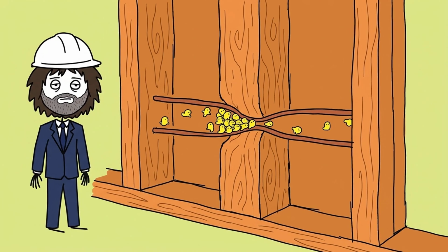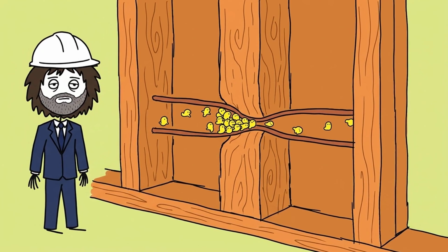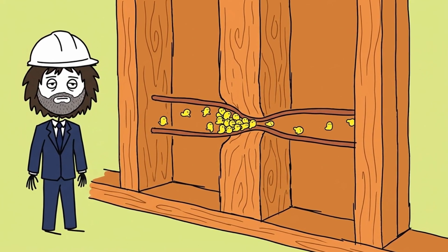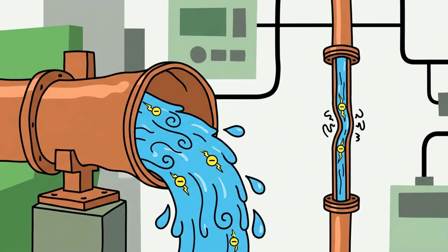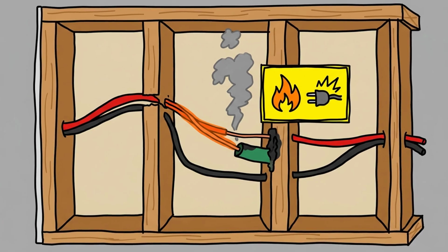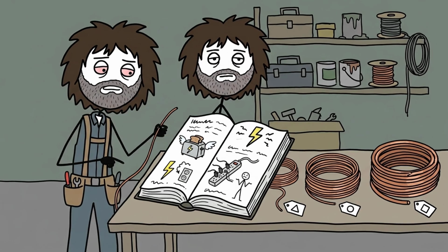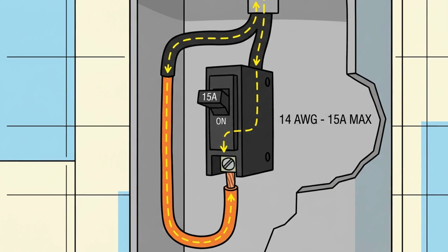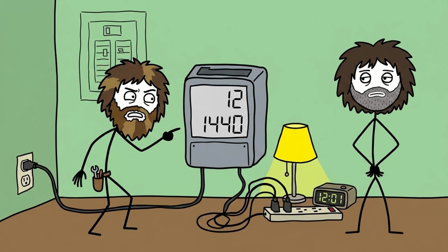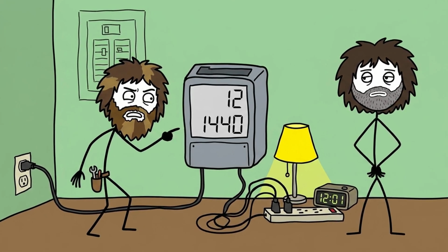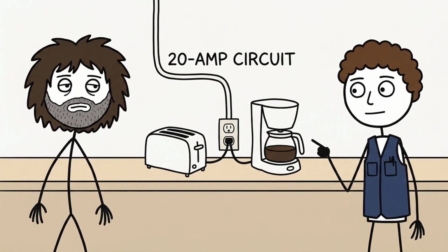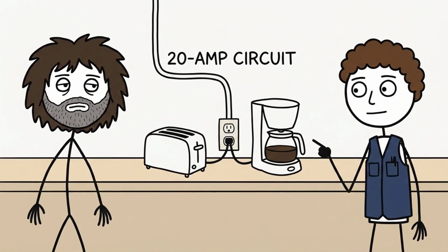Instead, current passes through an internal bimetallic strip made of two distinct metals bonded together, expanding at different thermal rates when heated. As 22 amps flow through the bimetallic strip, resistance causes the metal to warp. Over 10 to 60 seconds, the strip bends far enough to trip a spring-loaded mechanical latch, snapping internal contacts open and cutting off power before wall wiring reaches ignition temperature.